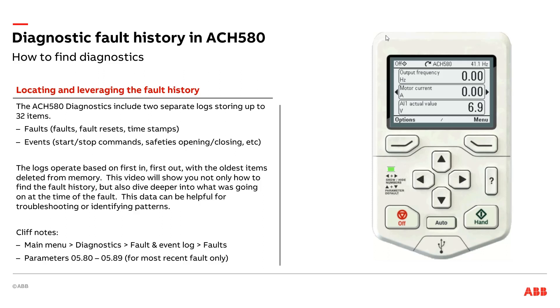The drive can actually hold 32 of the most recent faults and events. In today's video we're going to focus on the fault aspect of the events. A fault is something that prevents the drive from running — not a normal safety, not a high static or vibration trip safety opening up, but something within the drive stopped it from running. Maybe the drive was too hot, maybe there was a ground fault because a wire got worked its way loose and or shorted out. Let's dive into the faults of the ACH 580.